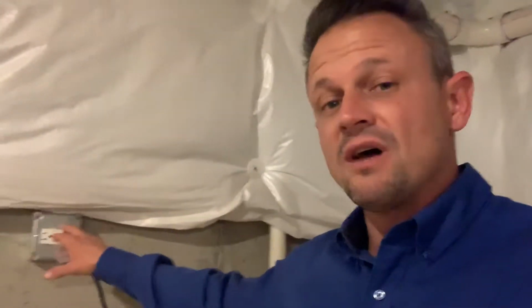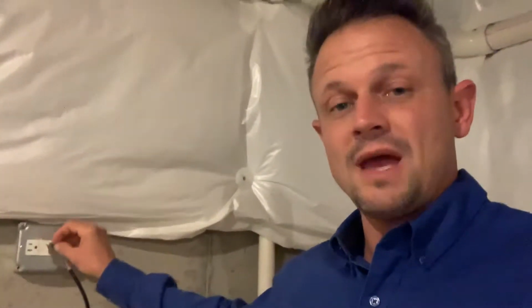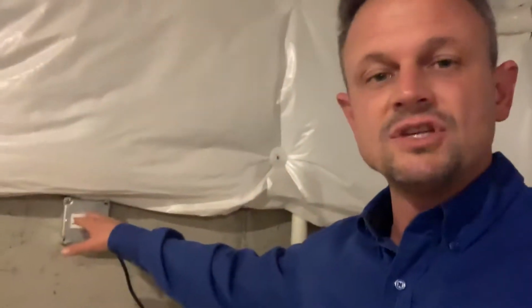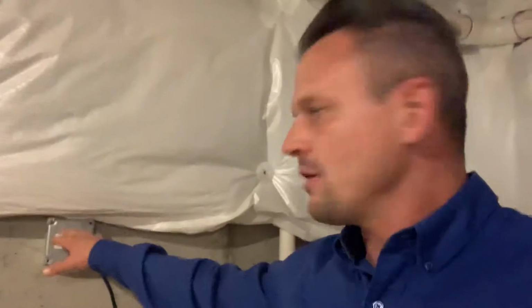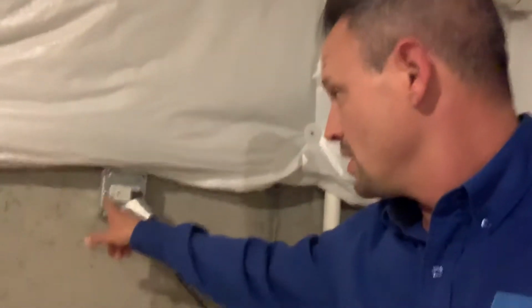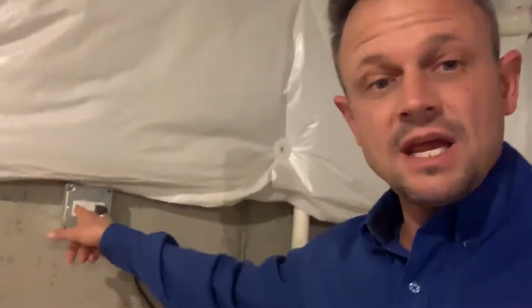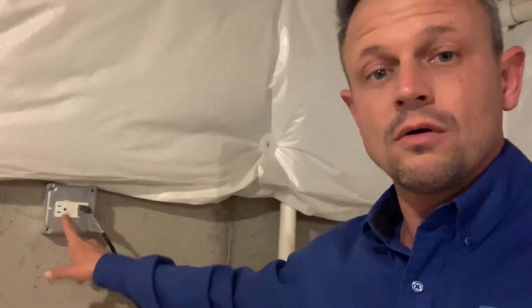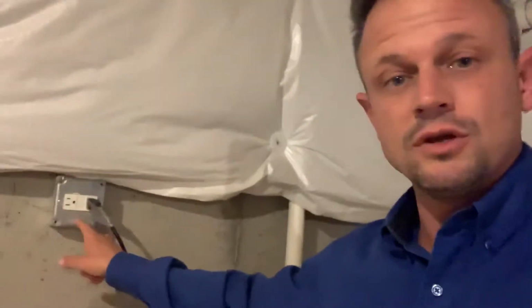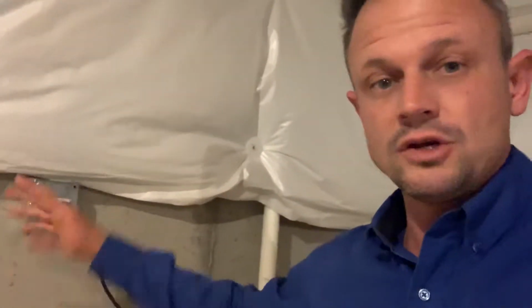because it's kind of counterintuitive. These GFI outlets are actually made to sense a spark or something grounding out. And an electric motor, which a sump pump has, has a spark to start. So it's a little counterintuitive. It's a code requirement, but if you have a GFI here, go to Home Depot or Menards and just get a regular 15 amp square receptacle. This way you can use this metal Garvin cover, and you're just swapping it out. It's some basic electrical.